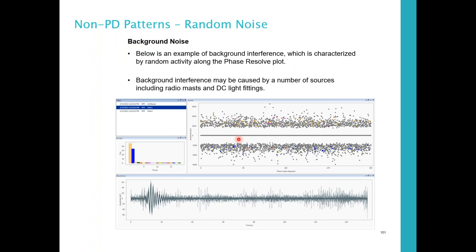Non-PD patterns are random noise, scattered randomly. No clusters really forming. Positive and negative amplitudes, and no sudden rise times. Repeated signals. So this is all noise.